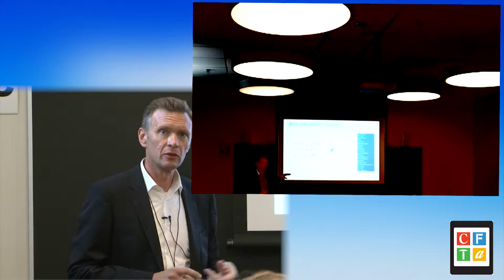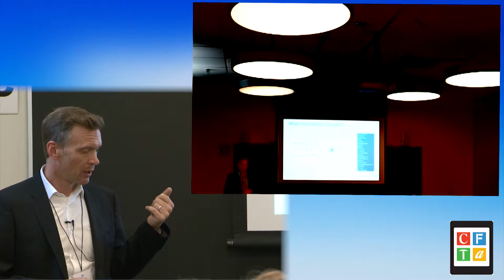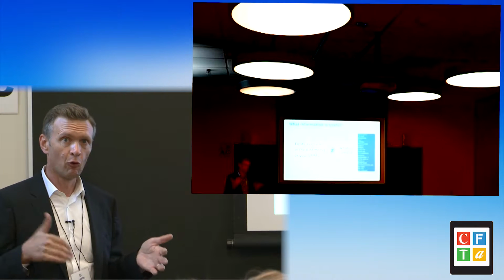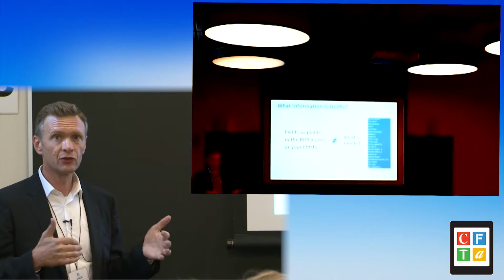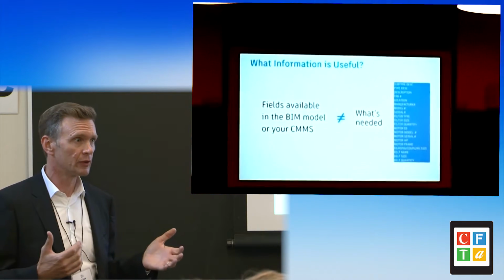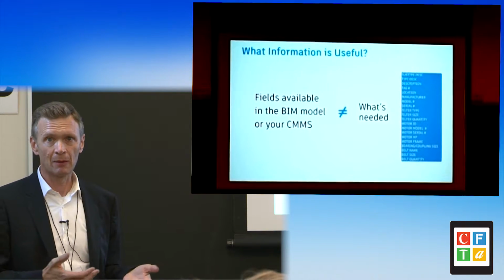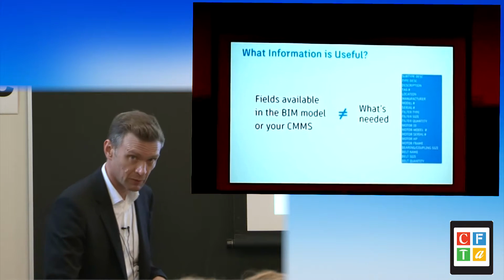And then within that, there's going to be a set of categories of information that you want. I mentioned some earlier: horsepower on a motor, pressure on a valve. Those are the things you want. What we've seen characteristically is that this number is somewhere between about 10 and 25 for a specific piece of equipment, depending on the nature of that piece of equipment and its complexity of operations. So if you see somebody with a model that's got hundreds of fields, you should be somewhat circumspect about whether or not you need all of those, and that may be an opportunity to streamline the experience later on.